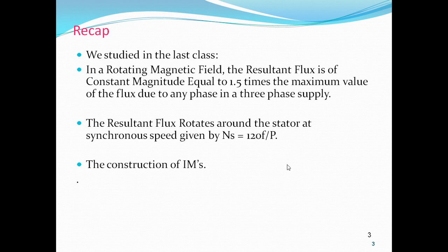So that from this terminal box the user can connect to the supply. The three-phase stator winding is wound for a definite number of poles as required for the speed. Depending on the speed, the number of poles is designed. The greater the number of poles, the lesser the speed.